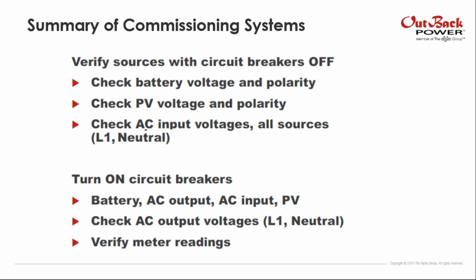Then for turning on the circuit breakers, first of all, remember the GFDI. So we will have to turn on the battery, the AC output, input, or PV. The correct way to do it is first GFDI, then PV array, then battery to inverter, and then AC breakers. And then you have to check all the AC output voltages and verify that you have the correct readings in your meter and in the screens and with the LED indicators.